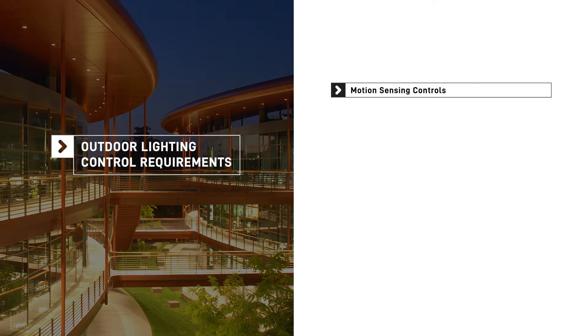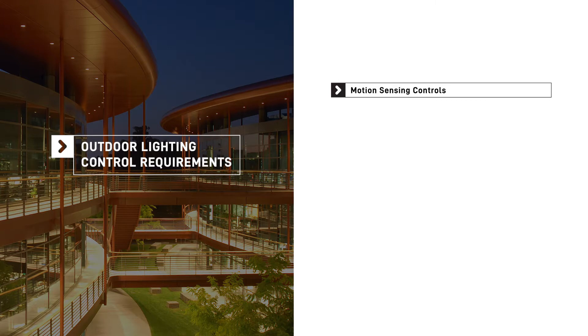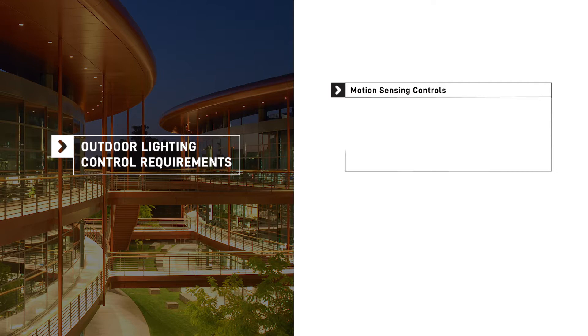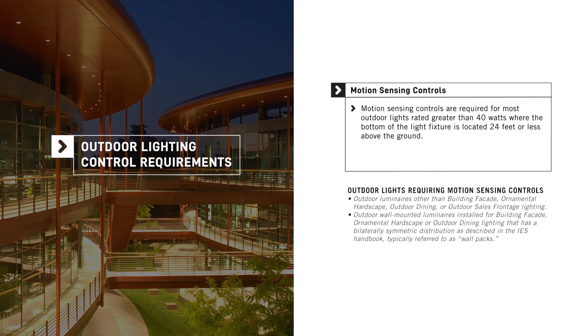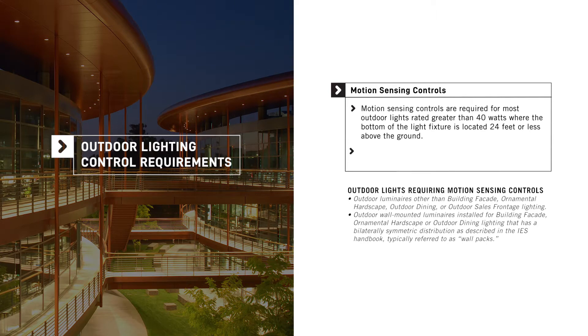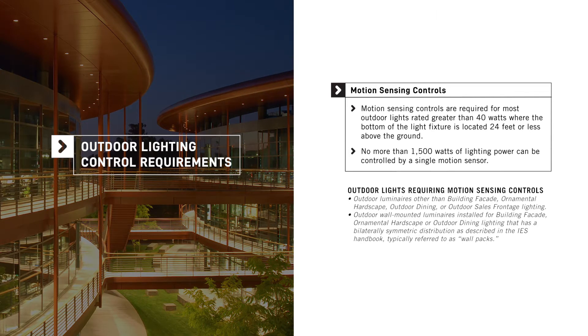Motion sensing devices control lighting based on detected occupancy by reducing or turning off the outdoor lighting in the area when that area is vacant. Motion sensing controls are required for most outdoor lights rated greater than 40 watts where the bottom of the light fixture is located 24 feet or less above ground. No more than 1500 watts of lighting power can be controlled by a single motion sensor.